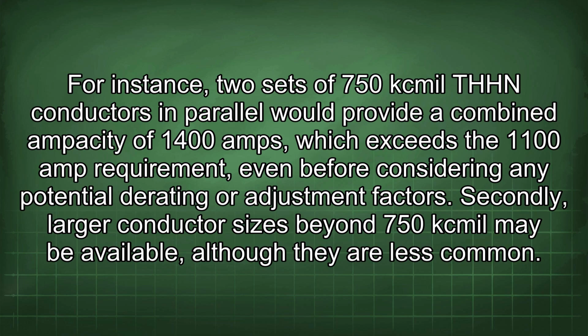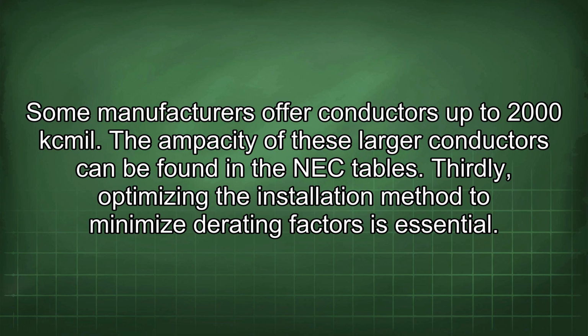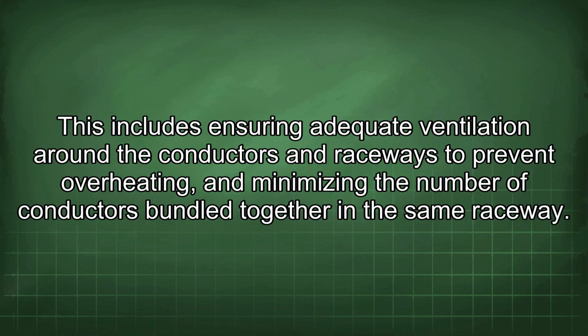Secondly, larger conductor sizes beyond 750 kcmil may be available, although they are less common. Some manufacturers offer conductors up to 2000 kcmil. The ampacity of these larger conductors can be found in the NEC tables. Thirdly, optimizing the installation method to minimize derating factors is essential. This includes ensuring adequate ventilation around the conductors and raceways to prevent overheating, and minimizing the number of conductors bundled together in the same raceway.